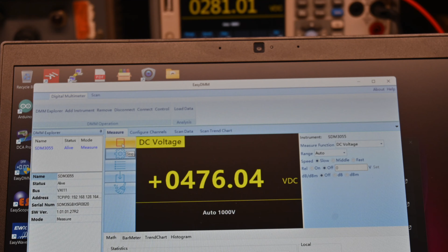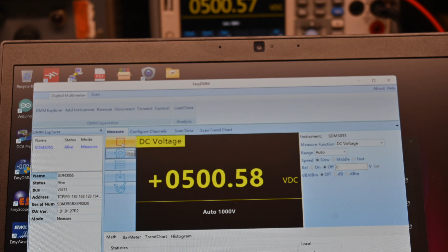And the other thing that I'll do, once it warms up, we'll put an AC voltmeter between the hot and the neutral to see what the line voltage dropped to after the CL80. So normal operations while it's warm. We can see that it's still climbing as the inrush current limiter warms up to normal operating temperature. I'm going to move the probe over to the other position where we should see our normally 480 volts. We're seeing 494 there. So we're pretty much at where we were when I was simulating this test with 117 volts line. So I'm going to say this likely dropped the voltage to around 117.